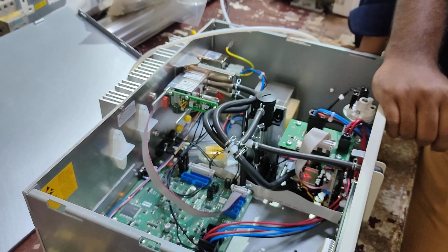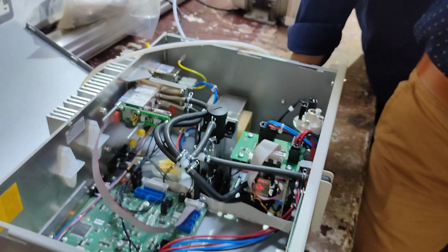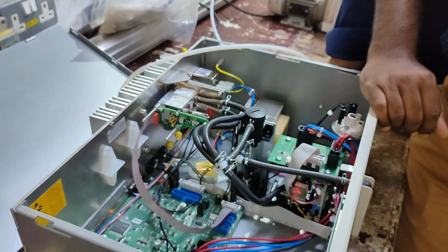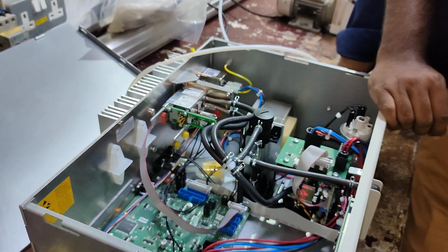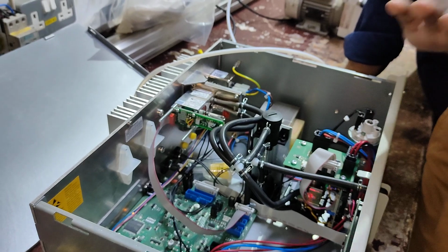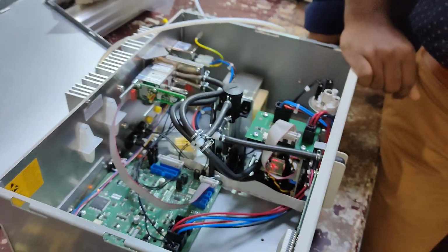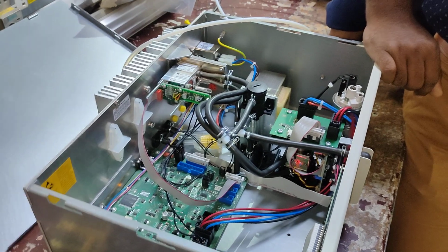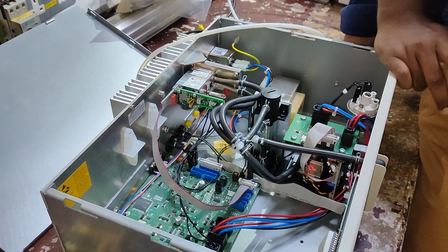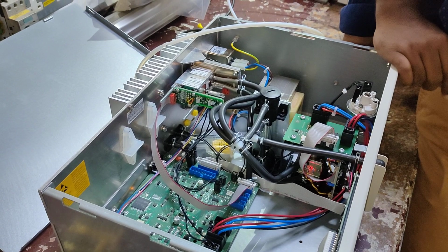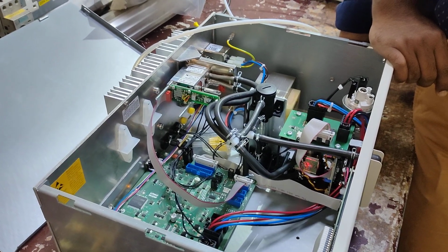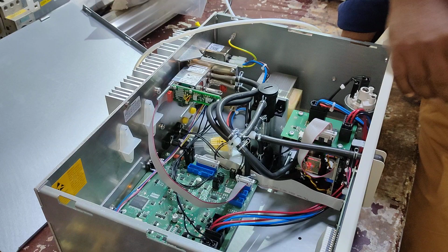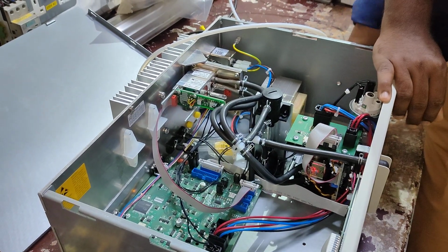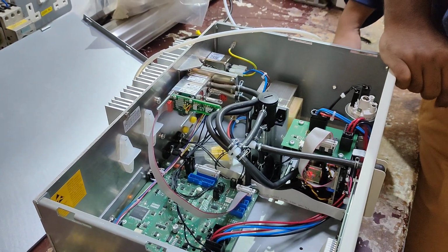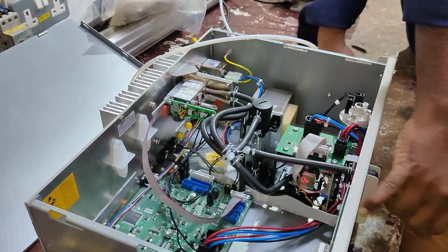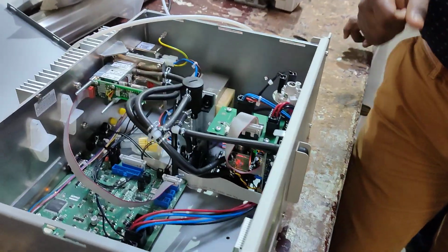In this analyzer, no reference gas is required. But how is the accuracy of this? It is accurate for all the CEMS wherever it is installed. I think with reference gas it would be more accurate. Nothing as such. With reference gas, you are always dependent on that cell. We don't know how much reference gas is sitting inside the cell, or whether the reference gas is active or not. Also, the resistance, the ohms, you can monitor from there. There is an option there, he will show you. You can run the pump now.